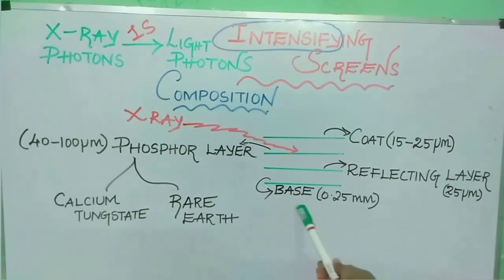Next is base, which is the supporting component of the screen made up of polyester plastic like the one used for radiographic film. The thickness of base is about 0.25 millimeters.